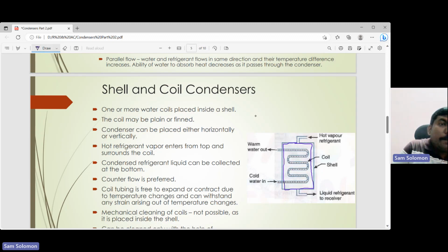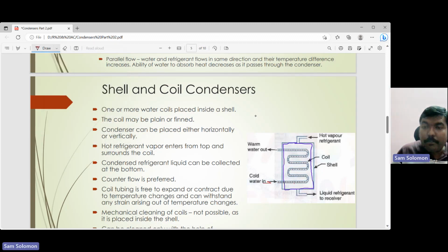Let me change the color again. So you have the water entering from below. Once again, it is passing through the coil. In this case, it is a serpentine coil again, and it leaves as warm water outside. This tubing, which we call the coil, has some flexibility, so it can either expand or contract due to the temperature changes, and it can also withstand any strain arising out of the temperature changes. You can place this either horizontally or vertically. The tubes or coils can have fins added, or they can be just plain. And as usual, you can have either the counterflow or the parallel flow, but the counterflow is preferred.